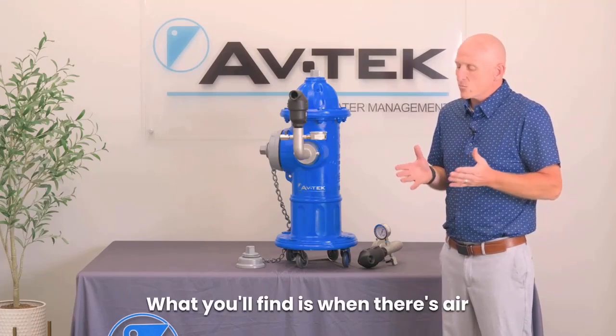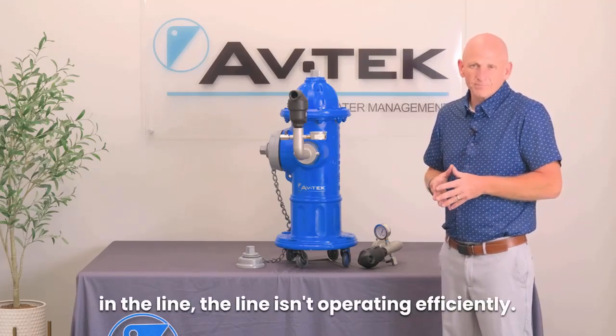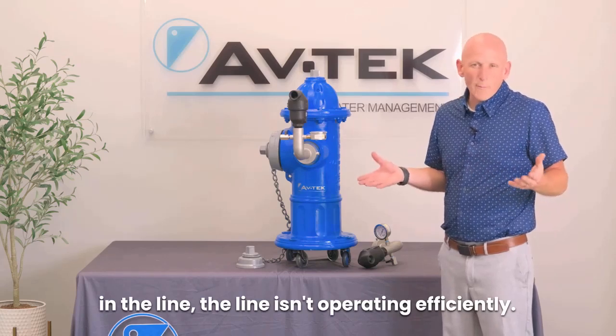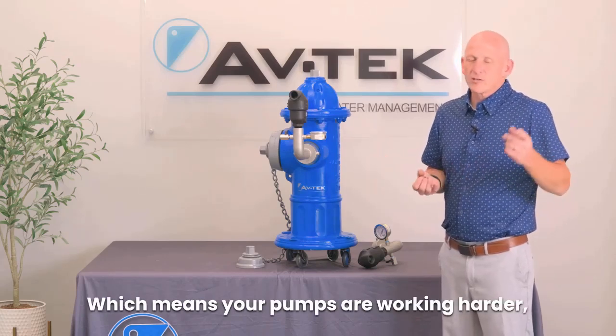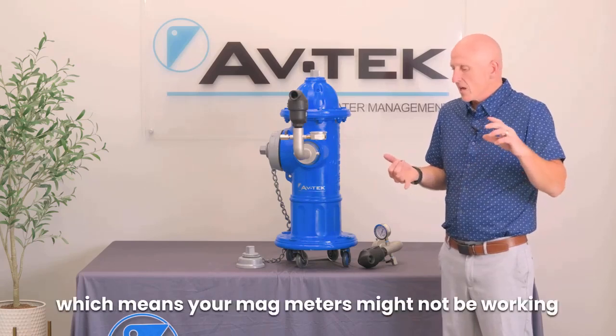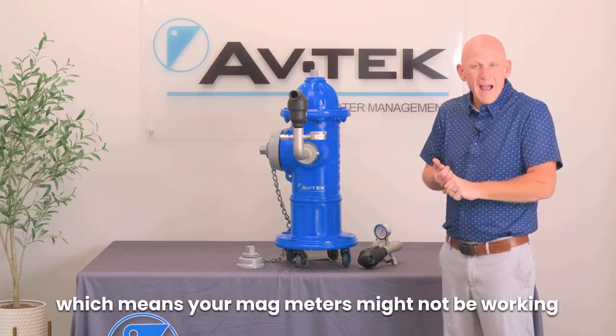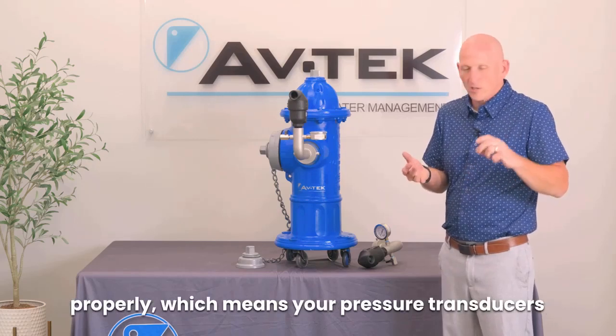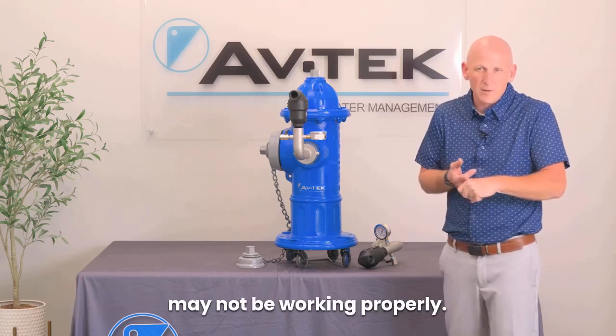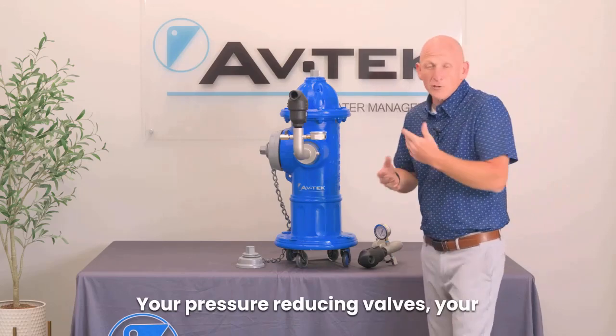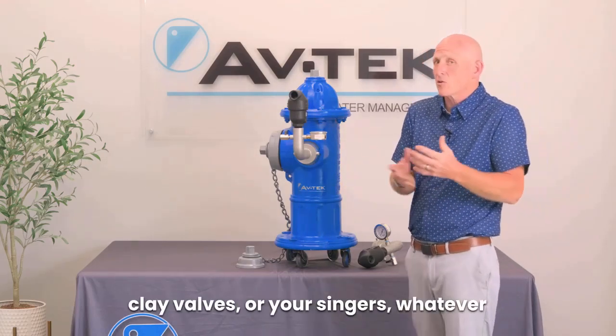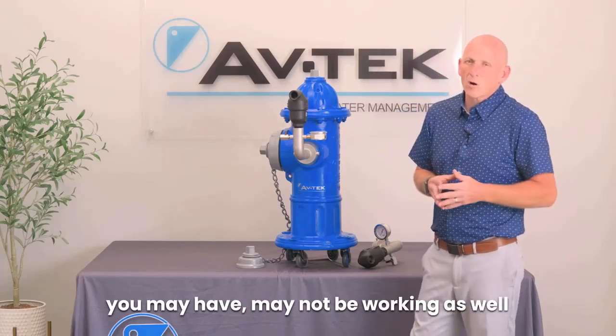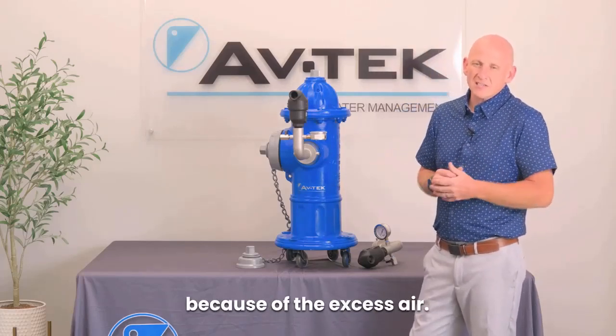What you'll find is when there's air in the line, it isn't operating efficiently, which means your pumps are working harder, which means your mag meters might not be working properly, which means your pressure transducers may not be working properly. Your pressure reducing valves, your Cla-Vals, or your Singers, whatever you may have, may not be working as well because of the excess air.